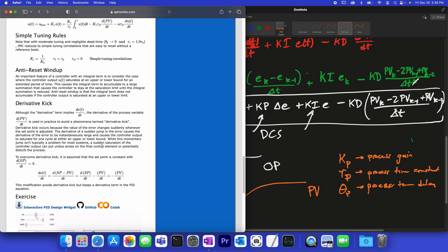We've already talked about anti-reset windup — basically it means the integral term stops changing when the actuator is at a saturation (upper or lower limit). And this also covers derivative kick — why we use minus d(PV)/dt instead of d(error)/dt.